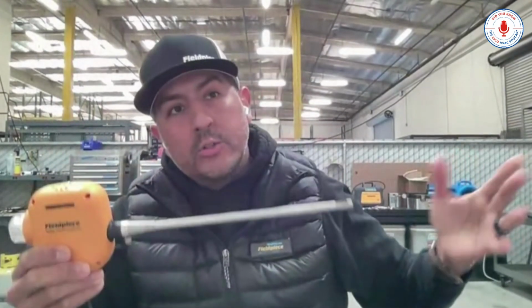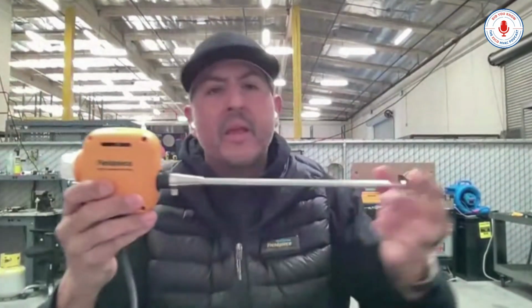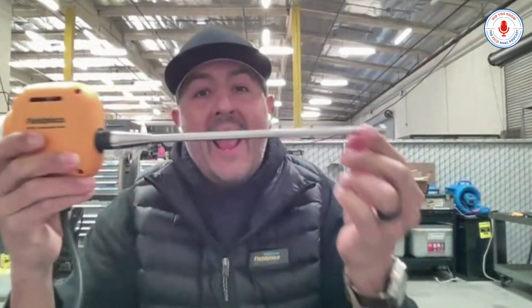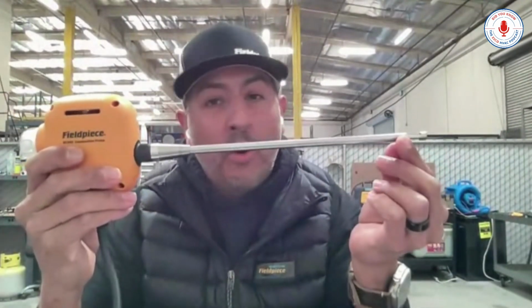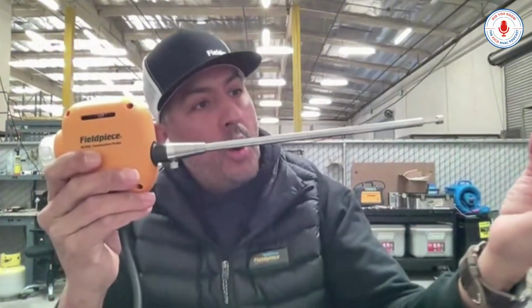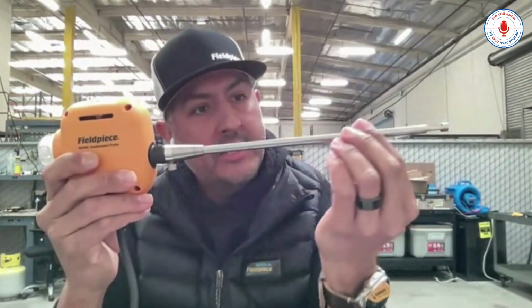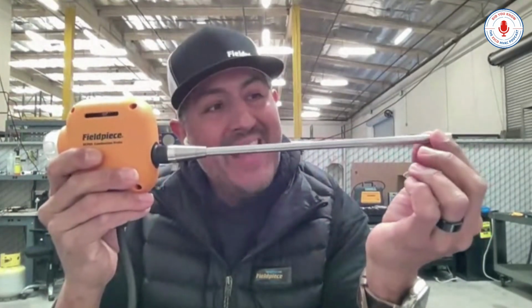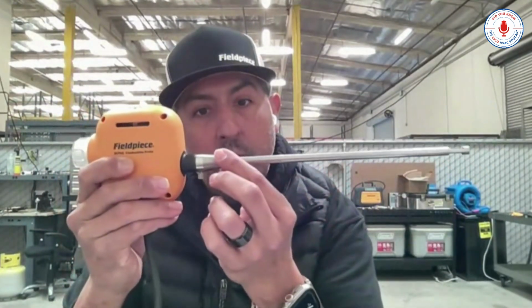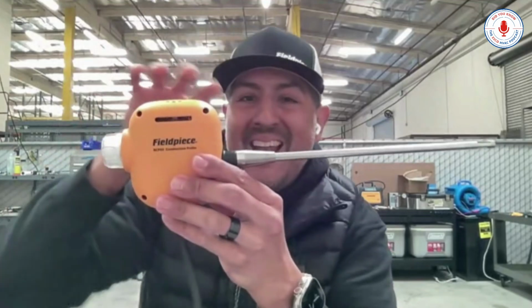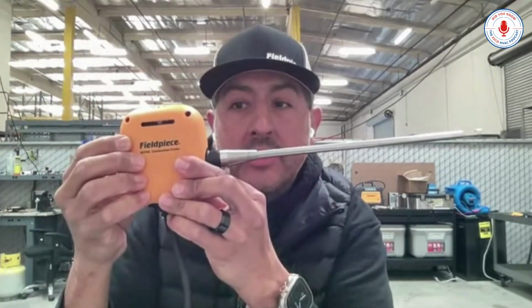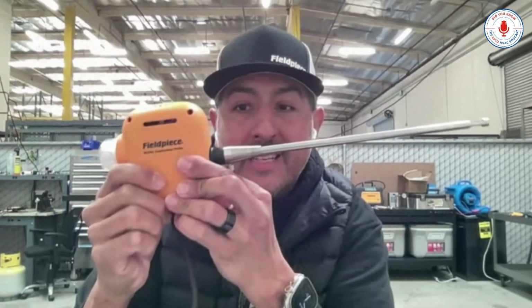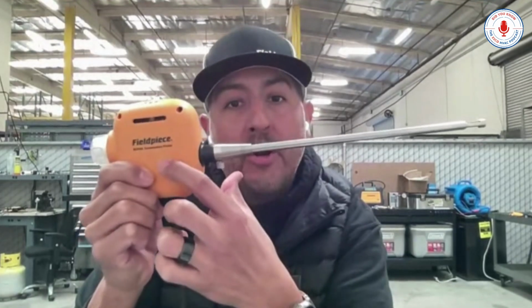Now, what hydrocycle pump does, you gotta love these marketing words, right? Sensor vault, hydrocycle pump. As you insert your probe into the flue, you are sampling, right? There's a pump in here that is pulling exhaust combustion gases and the water vapor into your probe. And in this handle, there's a mini condenser. And what this condenser does is that it condenses the water vapor here.